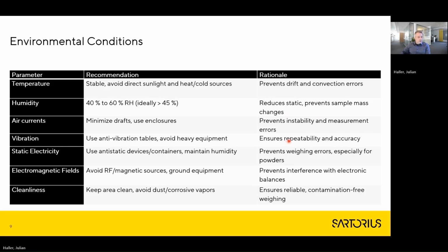Concerning air currents, drafts should be minimized by using enclosures and windshields. Concerning vibration, the use of anti-vibration tables is recommended, and heavy equipment should not be placed close to laboratory balances. Static electricity effects should be avoided by using anti-static devices like ionizers, anti-static containers, and a sufficiently high relative air humidity. Electromagnetic fields should be avoided, as well as magnetic sources, and balances should be properly grounded. Concerning cleanliness, like for any requirement in a laboratory, of course, the area near the balances should be kept clean, and dust as well as corrosive vapors should be avoided.